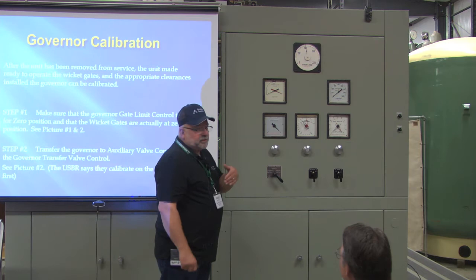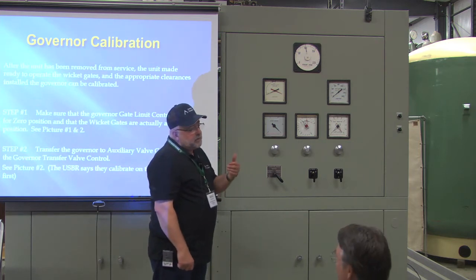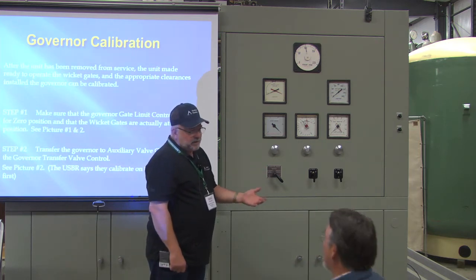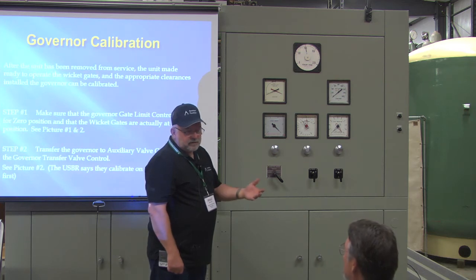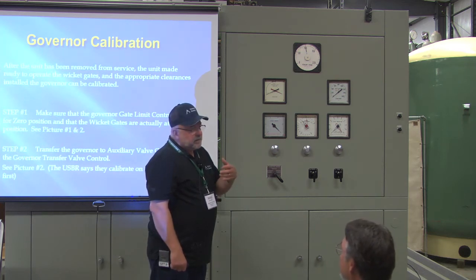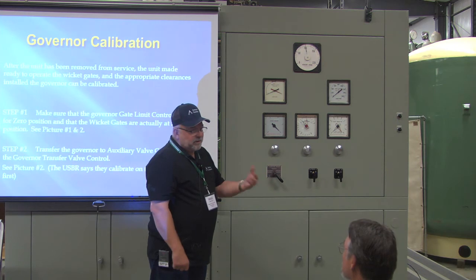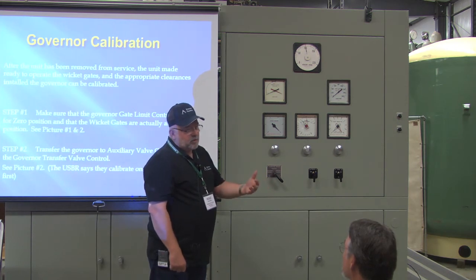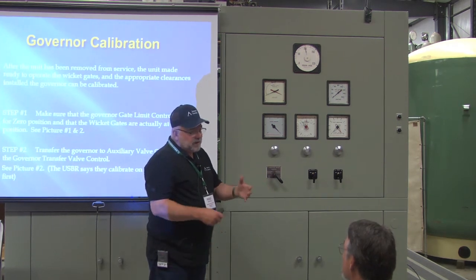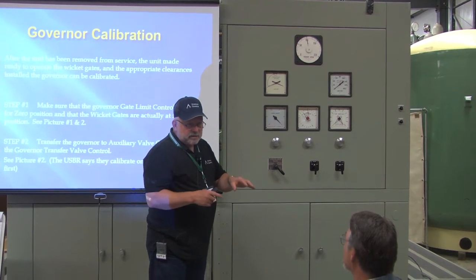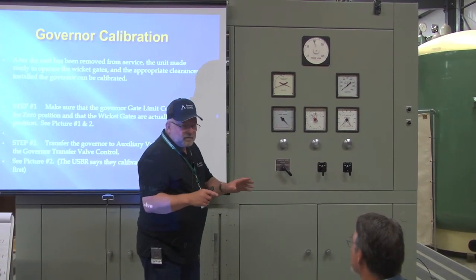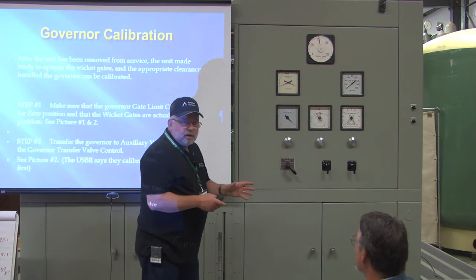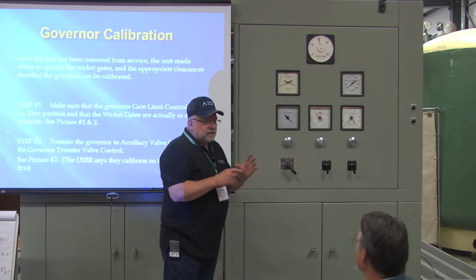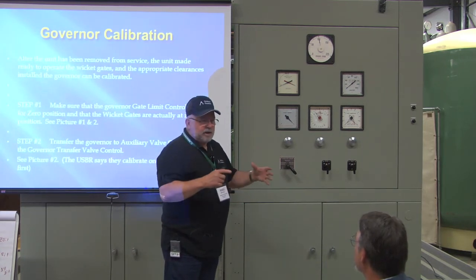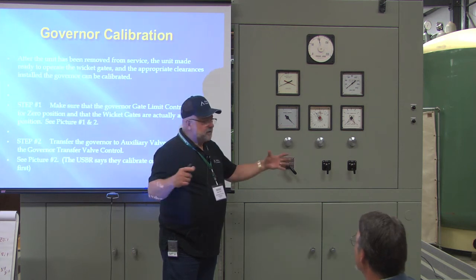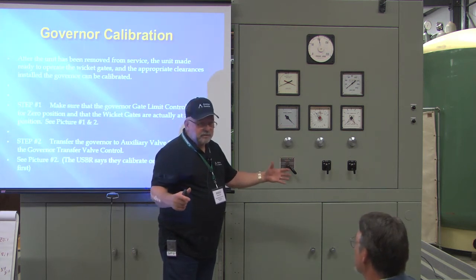but when you go over 150% of speed, it's not a good thing on a generator. When I was there, anytime we went 150 or more over speed, it was time to maybe pull a little iron and check keys and the poles and do a good inspection on the machine, because at those speeds, there's a lot of G's out there, you know. The big units, 500 G's out there on the outside.